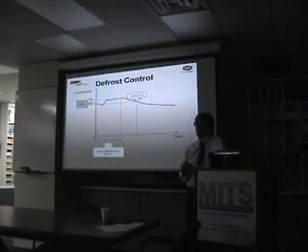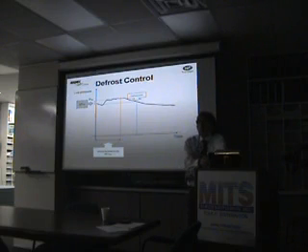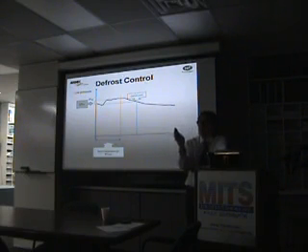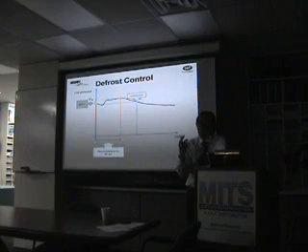Is it always time terminated or is the pressure terminated? When we invert the cycle it is time terminated. So it's a fixed time of 5 minutes. Exactly. But when we come back, we wait 600 seconds while the unit starts heating, and then we start the check again. And if we have a very quick pressure drop, we start again.